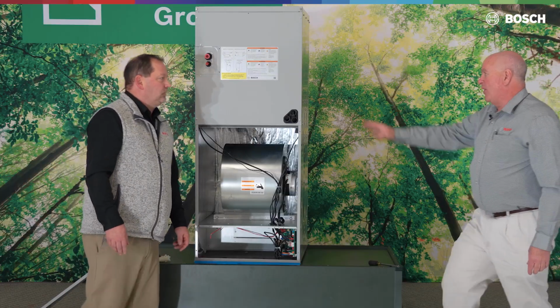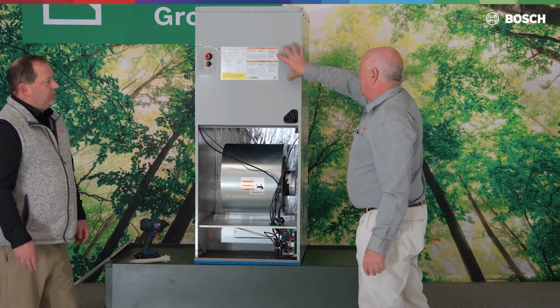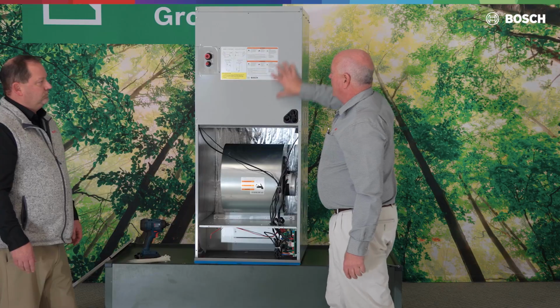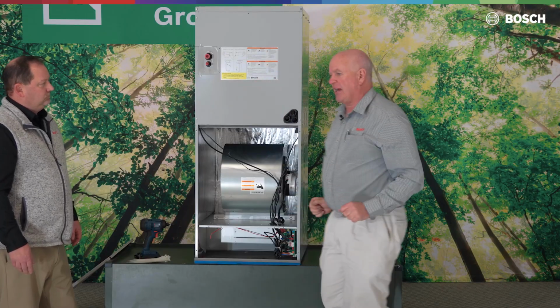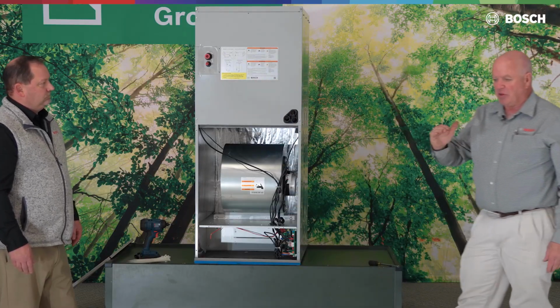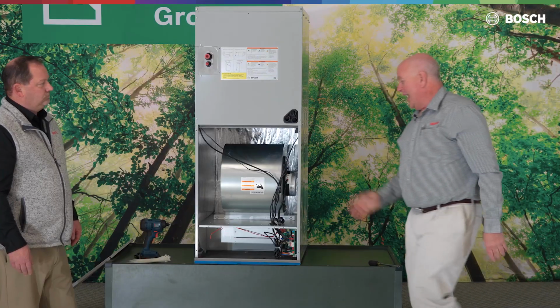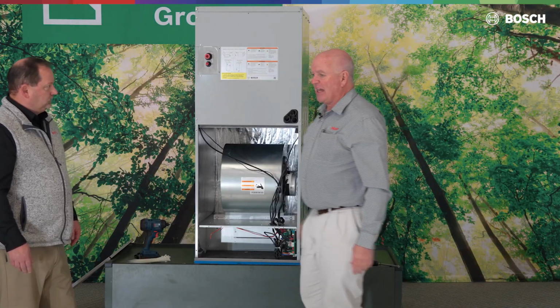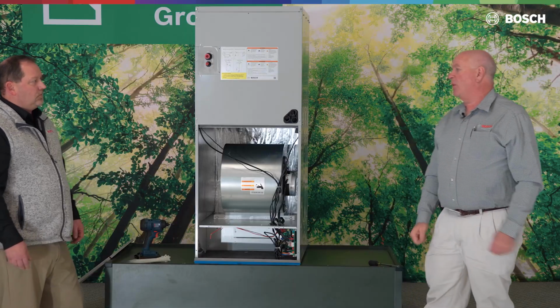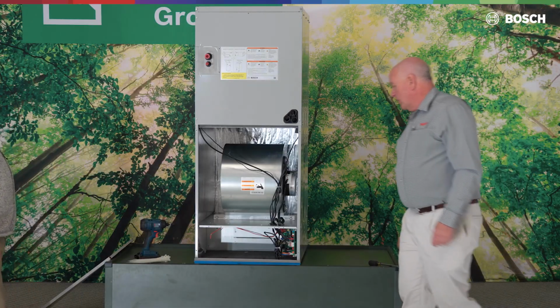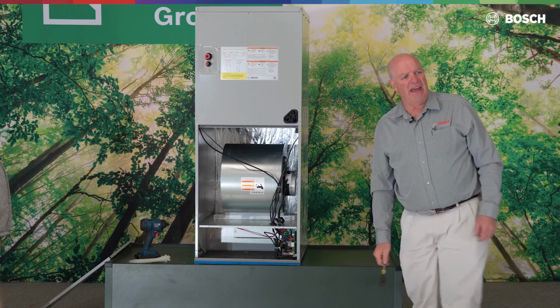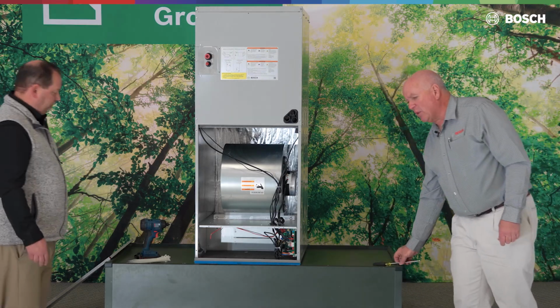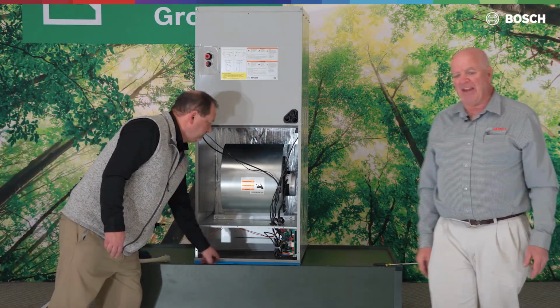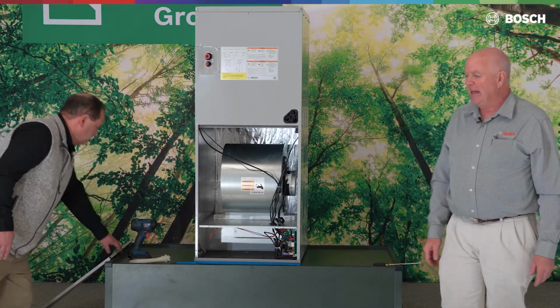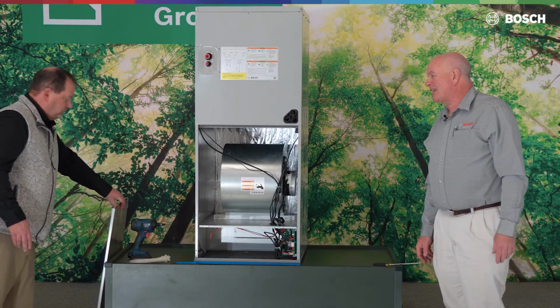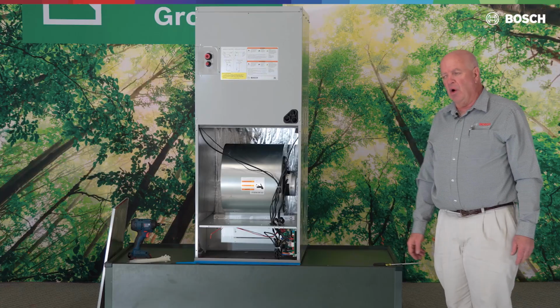Because of the way we generate our heat with the capacities of the coil in here, this is my source of where I get the heat from inside the space to go out to the compressor section to clear the coil, and we shut the outdoor fan off, which increases the heat. And that's another reason for the hydrophilic coating on the outside, so that water leaves the coil very quickly. Okay. So at that point, let's talk about some more things. How do we clean our coils? That's a good question. Guys, normally I'm going to say Fantastik, 409, Simple Green. Nothing very aggressive, no acid-based type of product. Low water pressure.